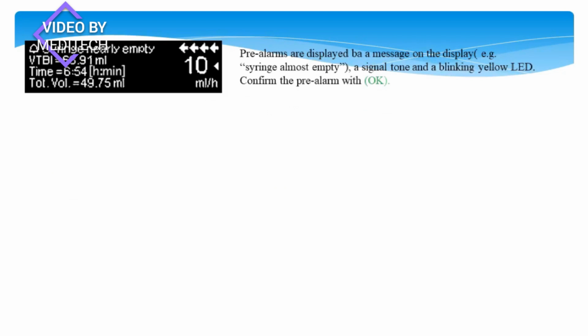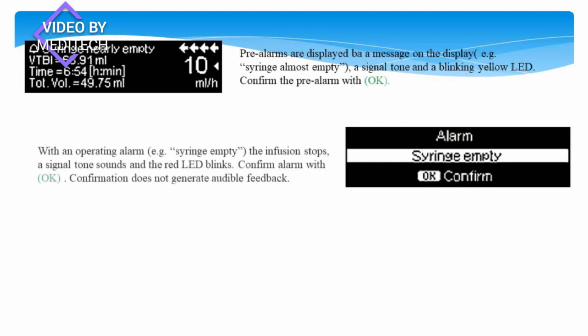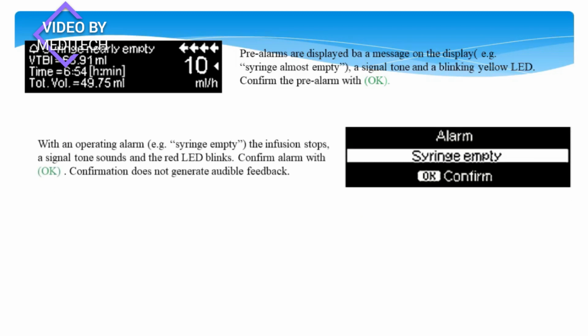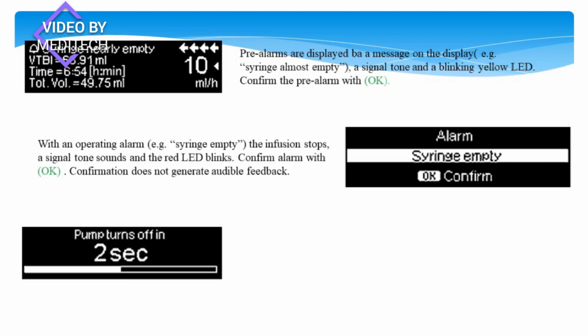Syringe nearly empty. Pre-alarms are displayed by a message on the display. For example, syringe almost empty. A signal tone and a blinking yellow LED confirm the pre-alarm; confirm with the OK button. Alarm, syringe empty alarm. With an operating alarm, for example syringe empty, the infusion stops. A signal tone sounds and the red LED blinks. Confirm the alarm with the OK button. Confirmation does not generate audible feedback.